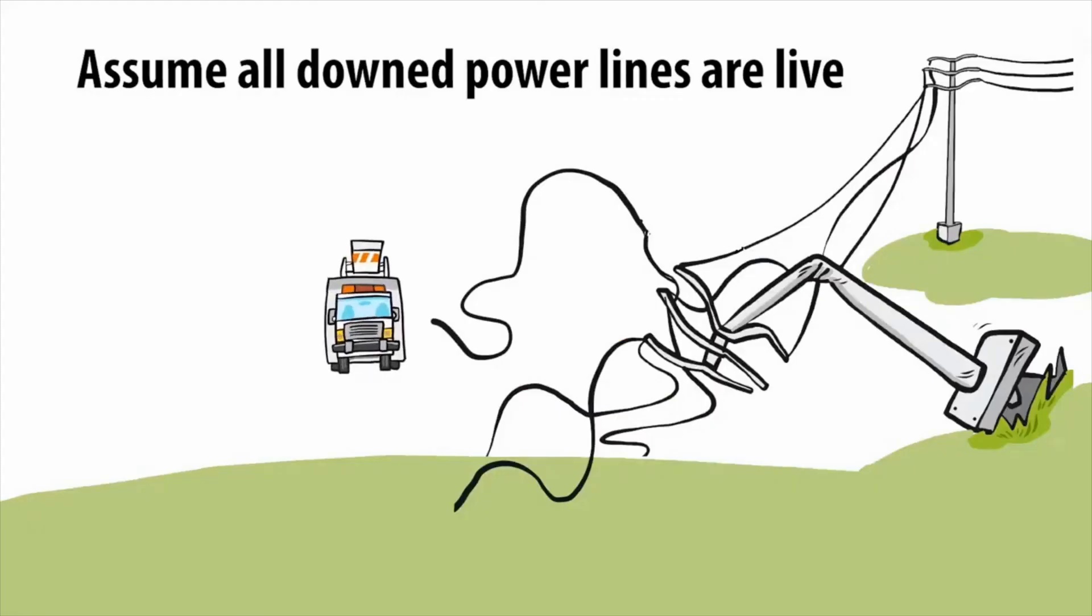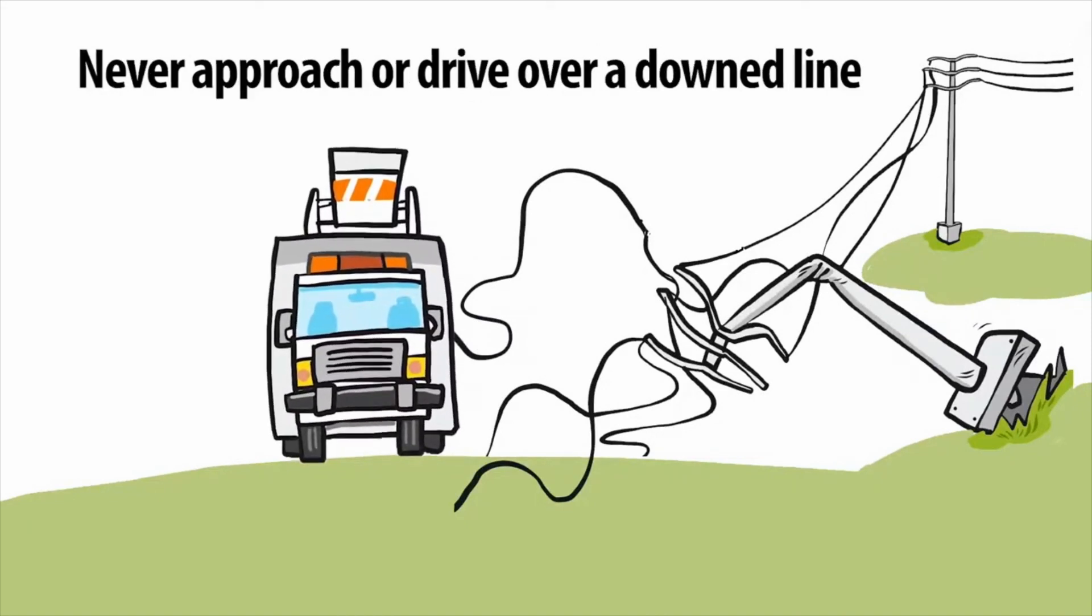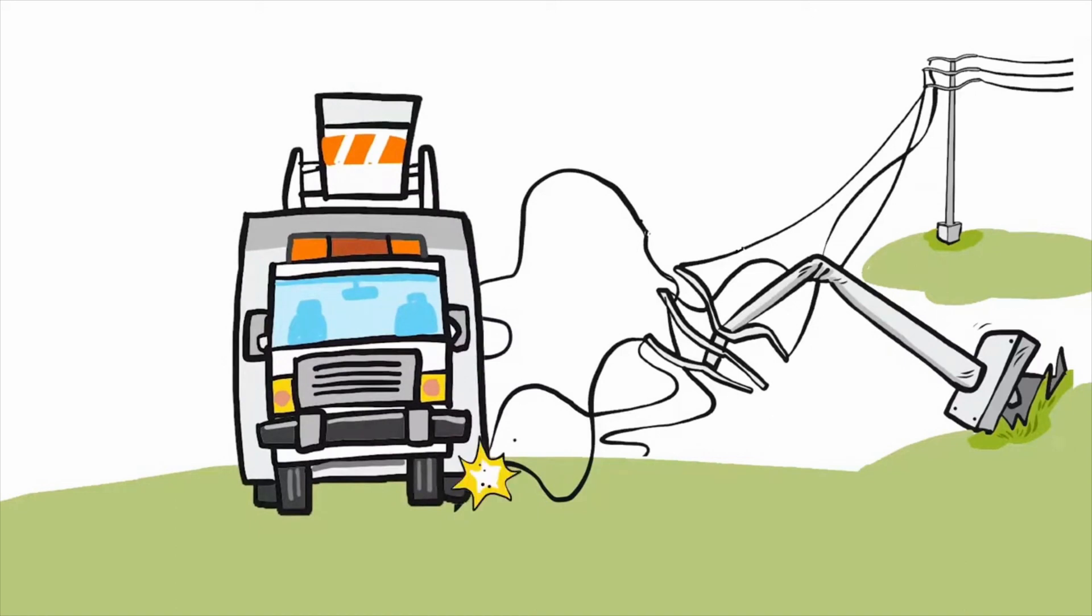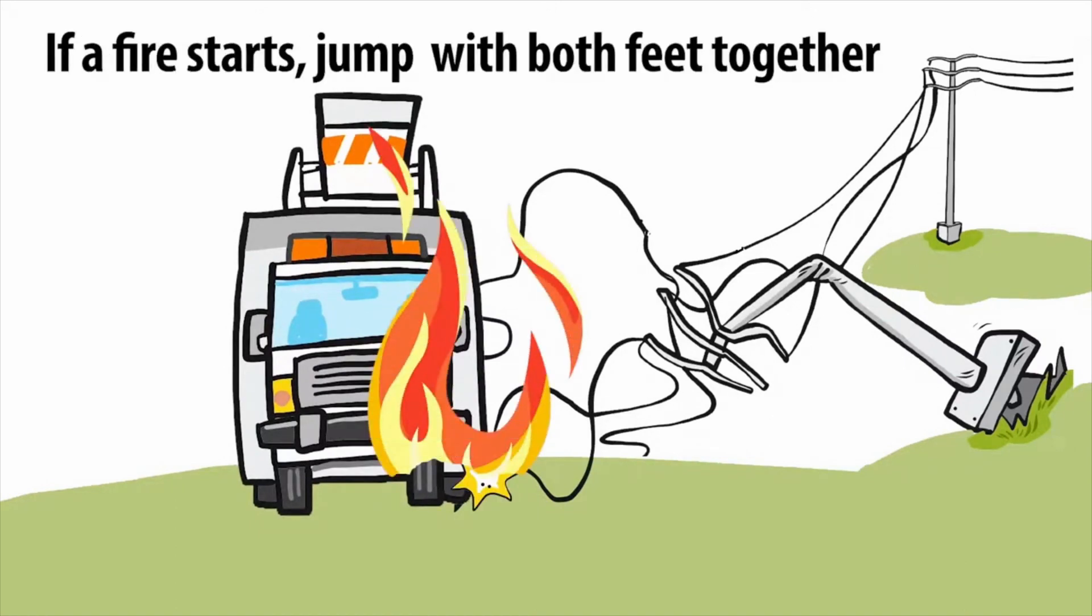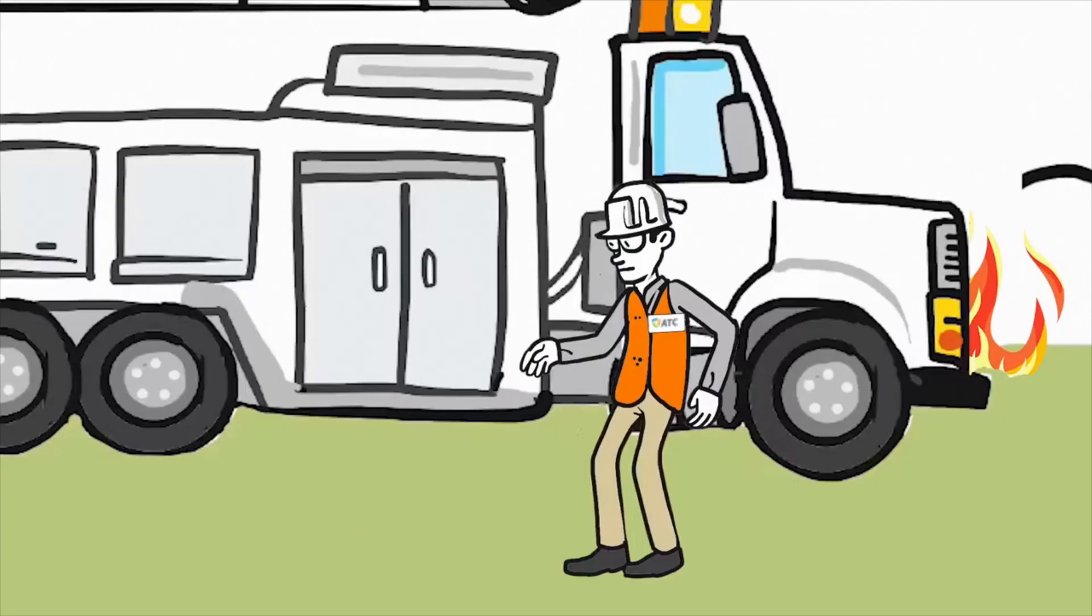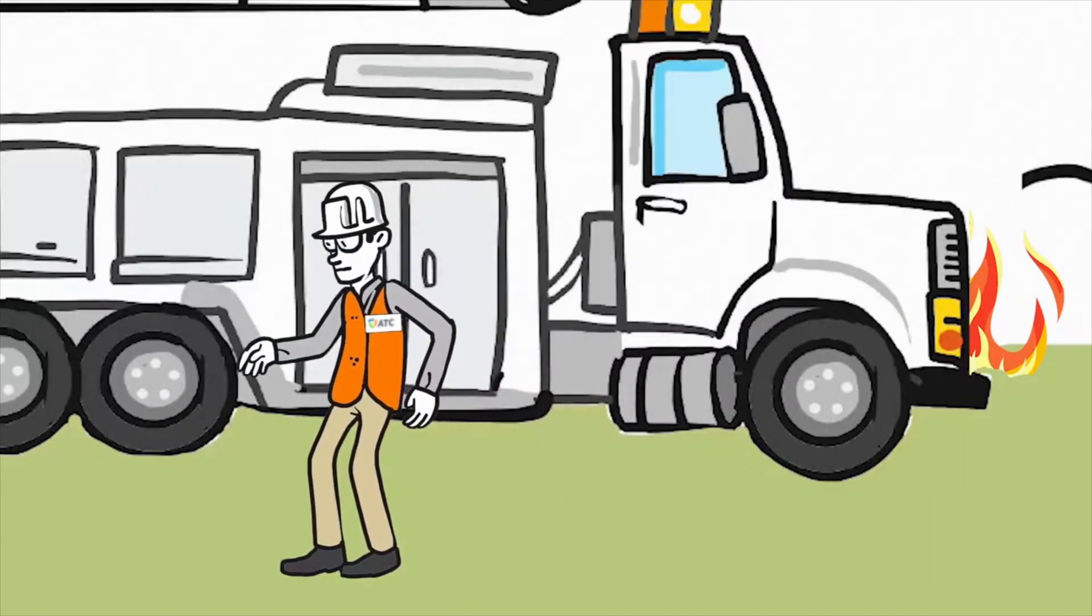Always assume all downed power lines are live and a hazard. Never approach or drive over a downed line. If your vehicle does contact a downed line, stay in the vehicle. If a fire starts, don't step out. Jump with both feet together, then shuffle away with feet together. Remember the step potential.